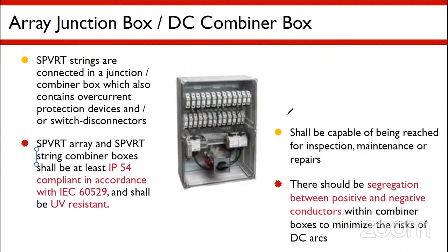Then as I told, array junction box means, instead of calling it a string, it is the total set of strings inside the array. Let's say there is a big array, and in that there are 4 strings. If 4 strings are coming into the box and then going out, in that case it is called an array junction box, because the entire box deals with this one table of array. If the array is not big and only the string is being controlled, then it is called a string junction box or string combiner box.